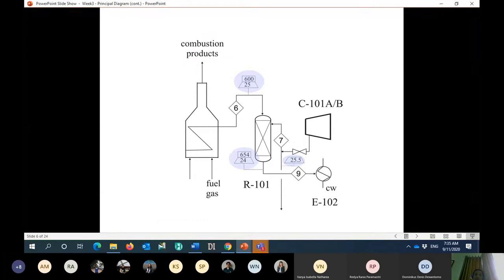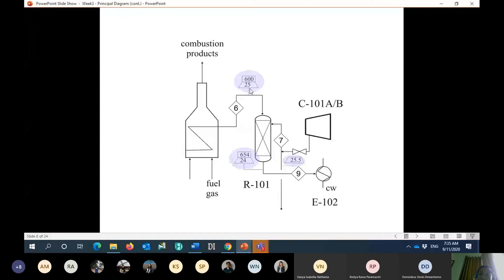For the utility, use conventional symbols or words. For example, LPS stands for low pressure steam, CW is cooling water, FG is fuel gas. If you use high pressure steam, you will have HPS — use the name or symbol already known by PFD convention. Sometimes in a PFD, instead of putting all information in the heat and material balance table, you can also highlight key values such as temperature, flow rate, or pressure directly on the diagram.